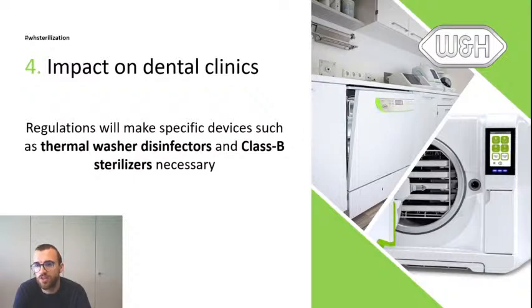So probably in the future it will be important to use automatic devices to clean and, if the regulation requires, also disinfect the instrument. Regarding sterilization, worldwide it's already required to sterilize instruments, but many regulations don't specify which type of sterilizer is necessary. Following the European standard, there are class N, class S, and class B sterilizers. If the type isn't specified, the clinic can use a class N sterilizer.